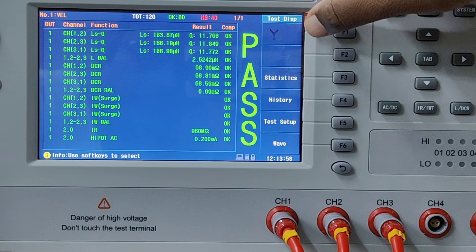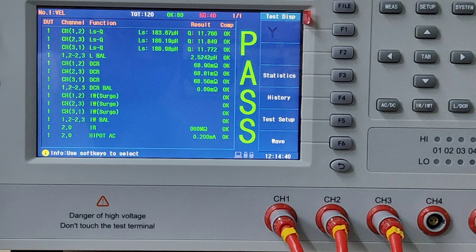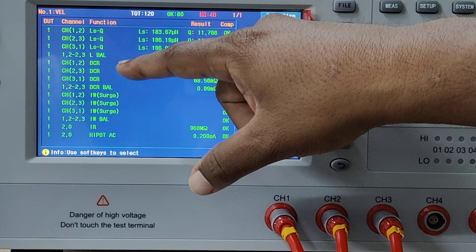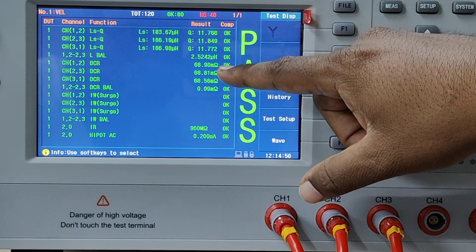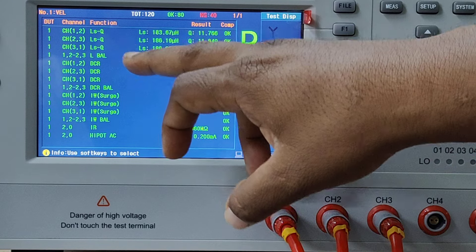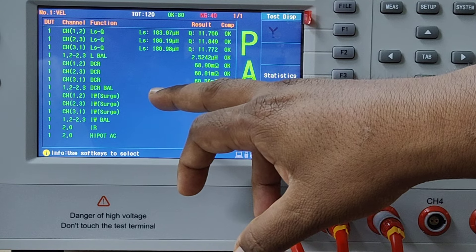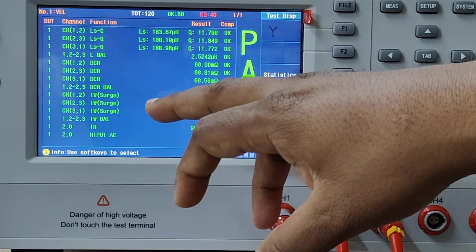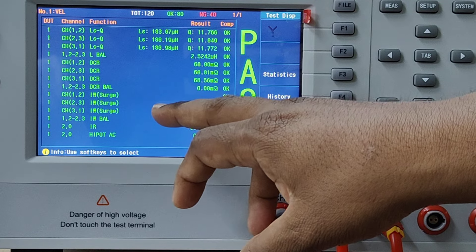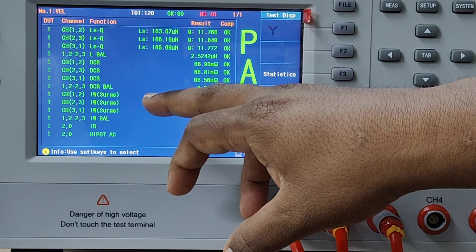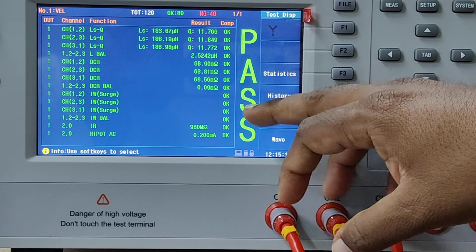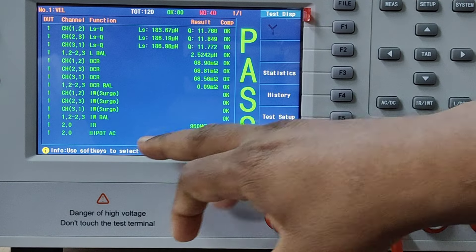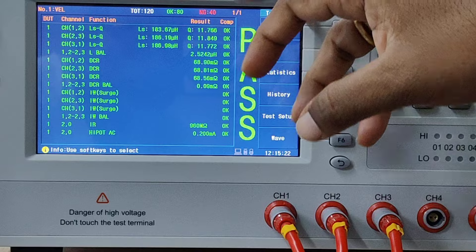Then comes the DC resistance measurement for the three phases — CH1 and 2, that is channel 1 and channel 2 measured resistance. If it is within the limit, you get OK for all three channels. There is also resistance imbalance, the same as inductance imbalance — between first winding to second winding, channel 1-2 and channel 2-3. Then comes impulse surge for channel 1-2, channel 2-3, and 3-1. If it is within the limit, it gets pass. Then you have impulse imbalance, which works the same as inductance and resistance imbalance.